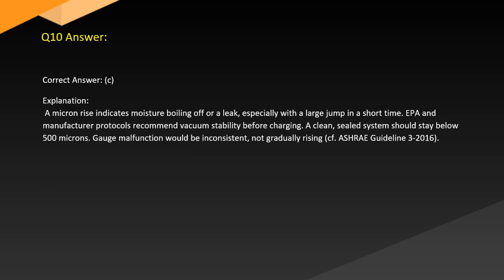Answer. Correct answer: C. Explanation. A micron rise indicates moisture boiling off, or a leak, especially with a large jump in a short time. EPA and manufacturer protocols recommend vacuum stability before charging. A clean, sealed system should stay below 500 microns. Gauge malfunction would be inconsistent, not gradually rising. Cf. ASHRAE Guideline 3-2016.